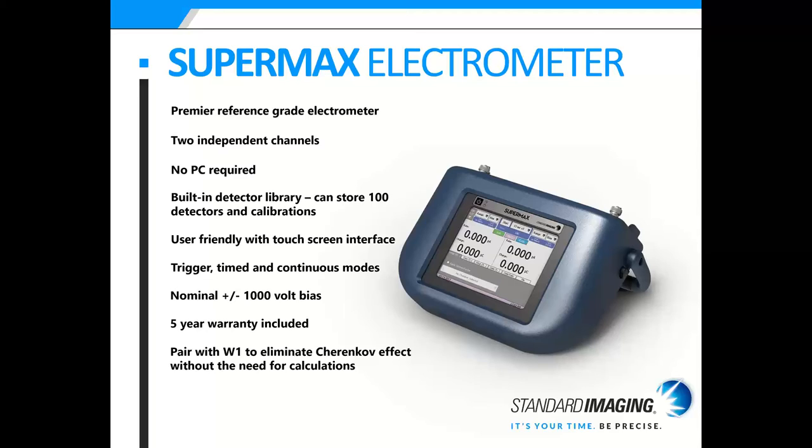No PC is required for the SuperMAX as it has a built-in detector library that can store 100 detectors and calibrations. It has a user-friendly touch screen interface with a stylus. Like the MAX 4000, it has three modes: trigger, time, and continuous, and a bias range of plus or minus 1000 volts. If you pair this with our W1 scintillator, you can eliminate the Cherenkov effect without the need for calculations.